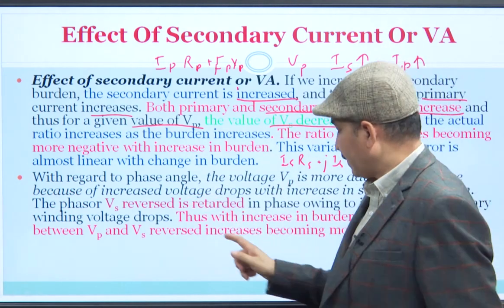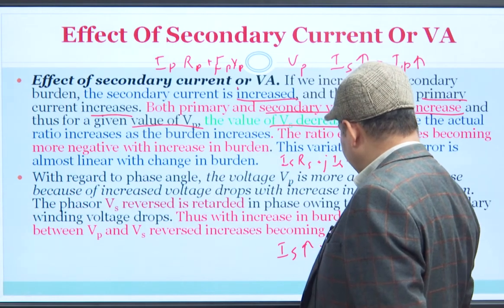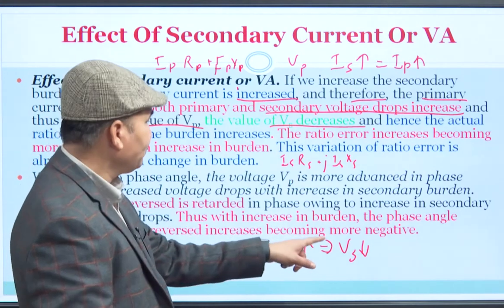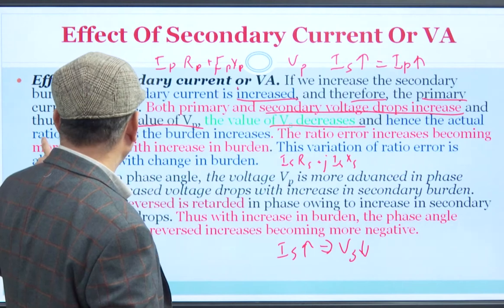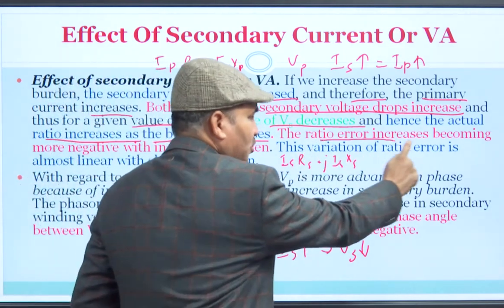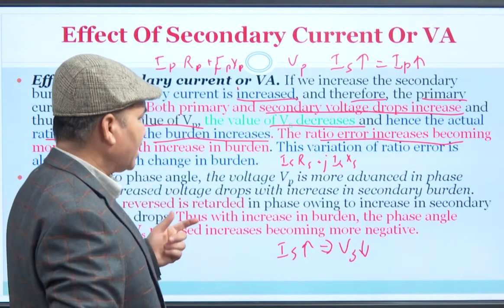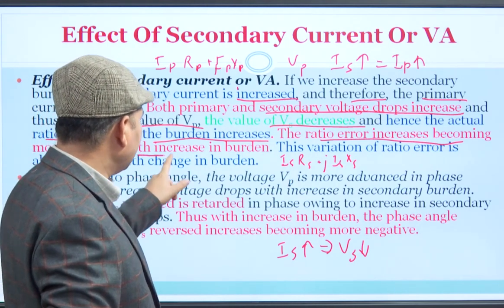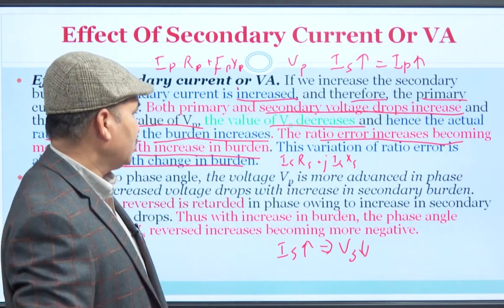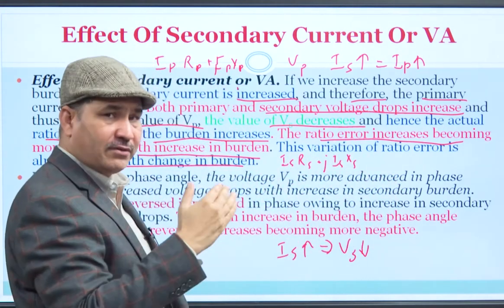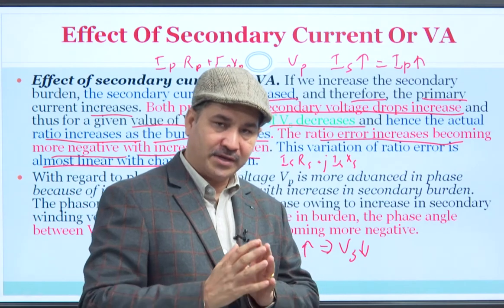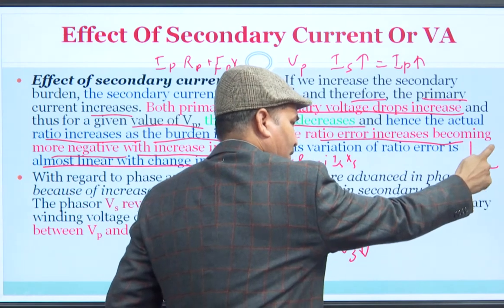With the increase in Is, it will lead to decrease in Vs, because Vp is fixed. So Vs will decrease, and hence the actual ratio R increases as the burden increases. The ratio error (R minus N) will also increase and become more negative as burden increases. This variation of ratio error is almost linear with the change in burden — as your burden increases, your ratio error increases proportionally. Therefore, unnecessarily large burden on the secondary should be avoided.